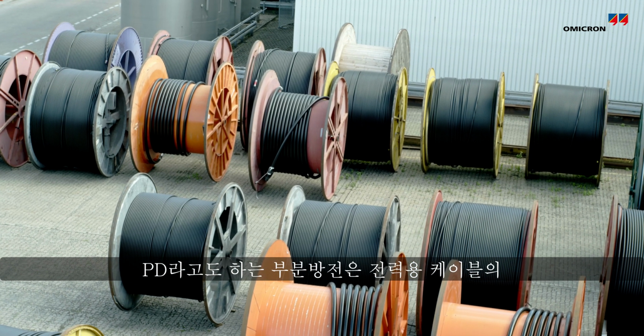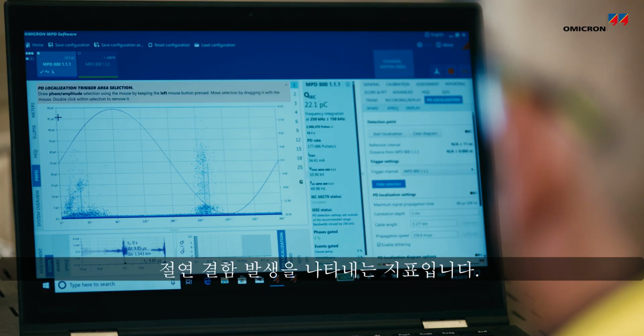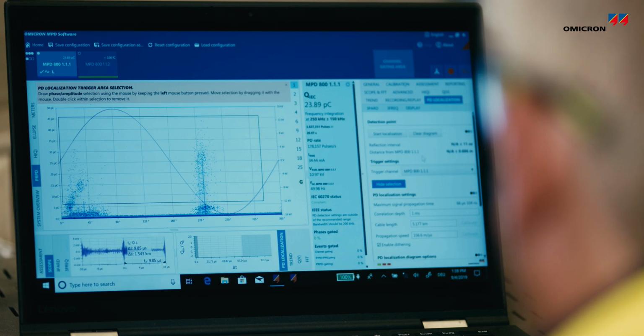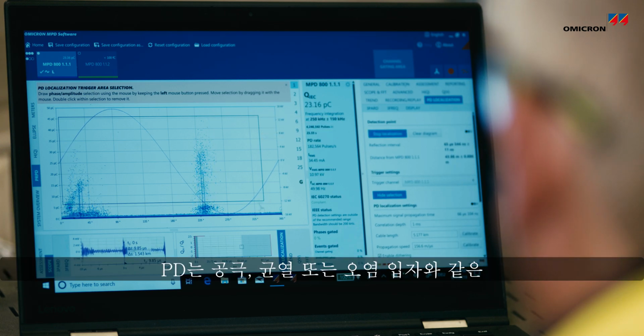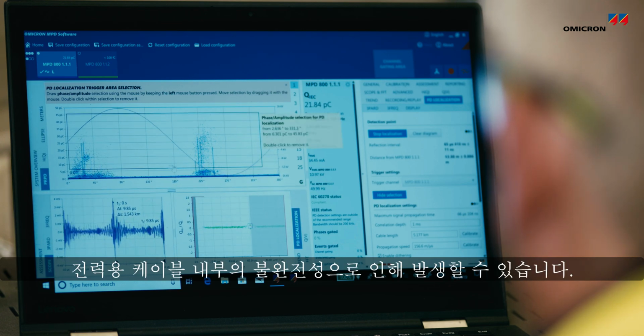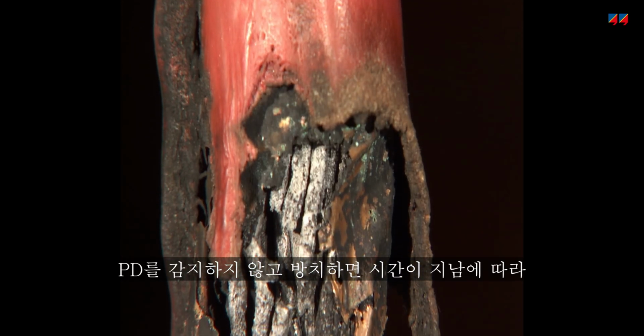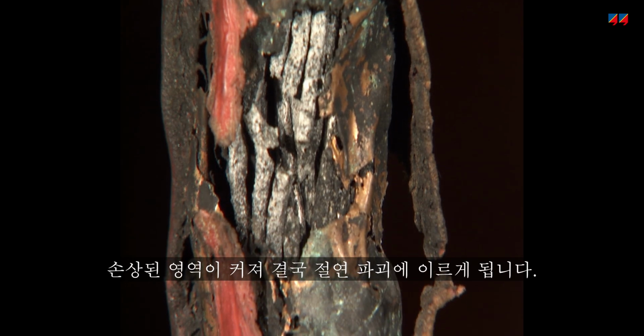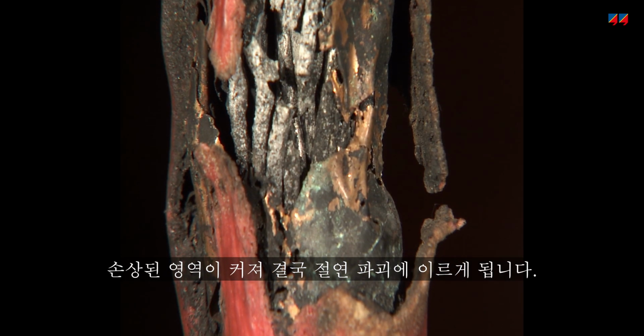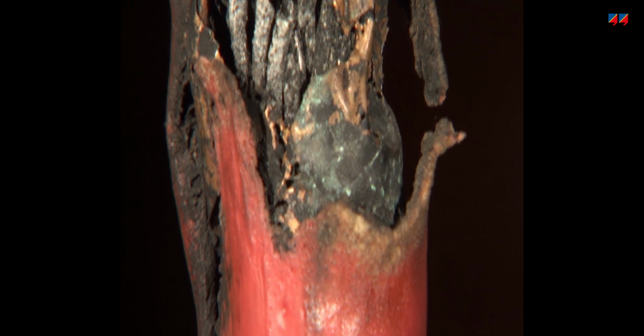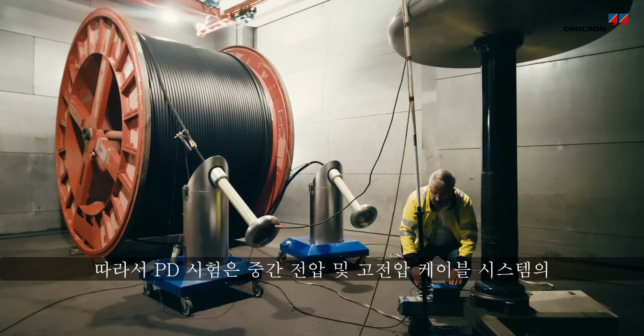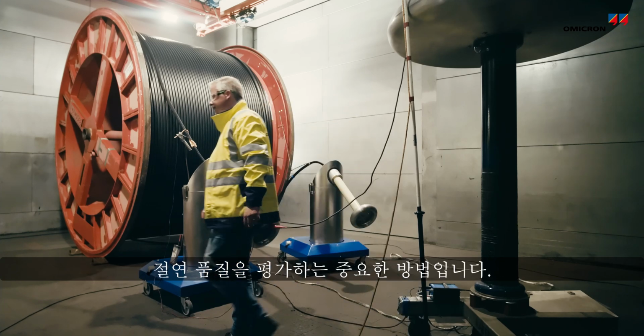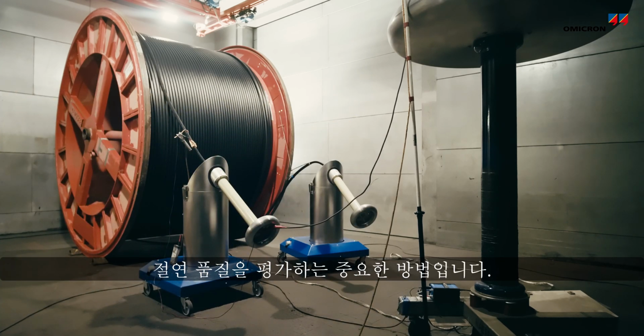Partial discharge, also known as PD, is a measurable indicator of developing insulation defects in power cables. PD can be the result of internal weak spots in power cables, such as voids, cracks, or contaminating particles. If not detected, PD causes damaged areas to grow over time, weakening the insulation to the point of failure. PD testing is therefore an important method of assessing the quality of insulation of medium and high voltage cable systems.